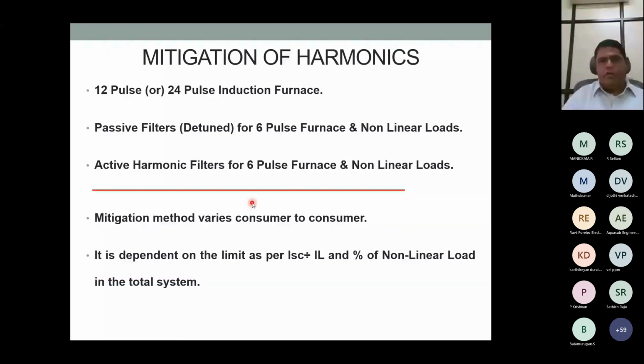So, mitigation of harmonics: how to mitigate harmonics in foundries? There are three methods. Most of the old furnaces are 6-pulse furnaces. Either they can be converted to 12-pulse or 24-pulse furnaces, and harmonics can be mitigated. This is one method. Another method is using passive filters, which are called detuned filters, with the 6-pulse furnaces and nonlinear loads.